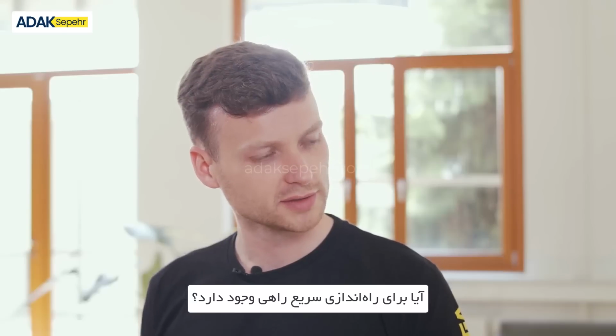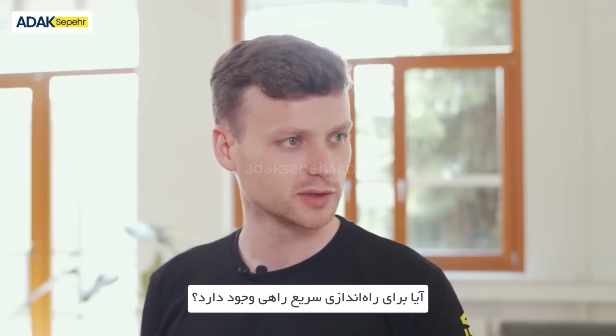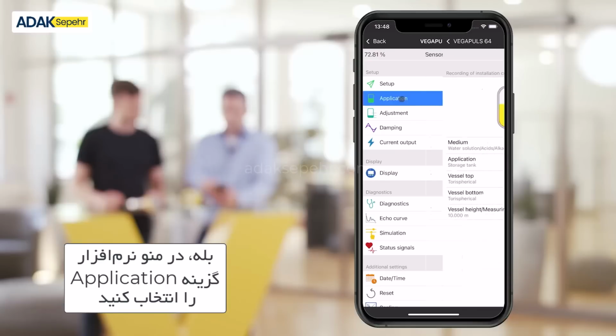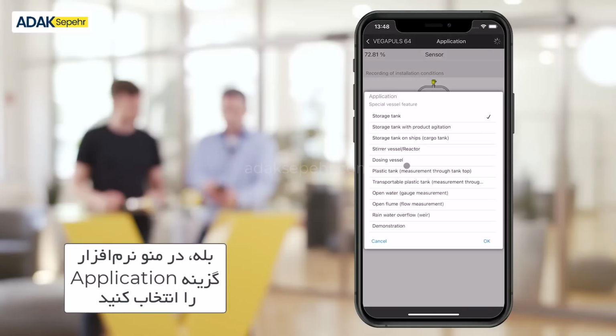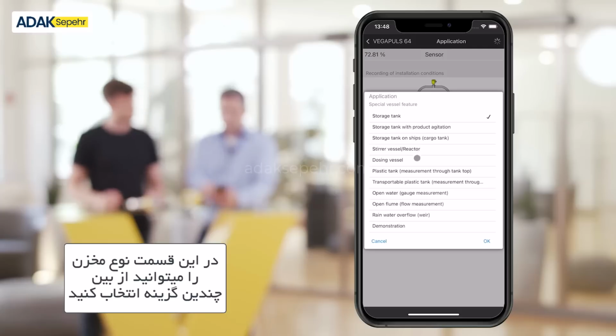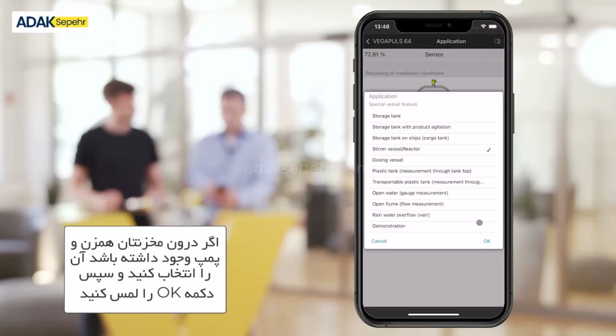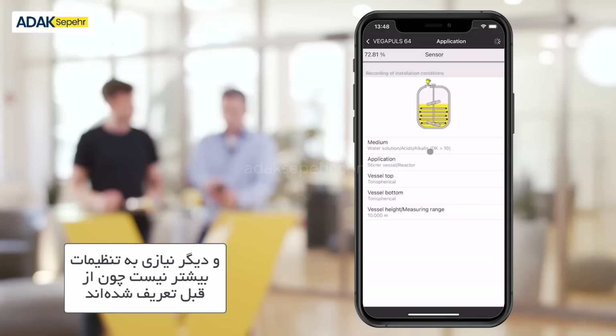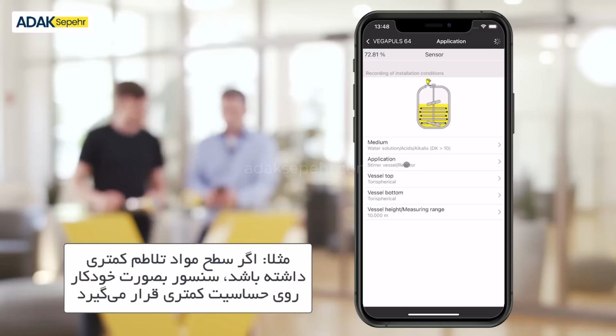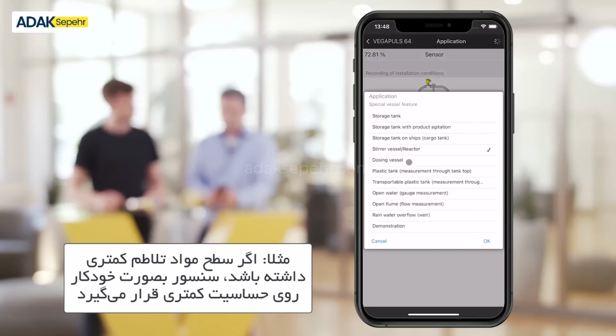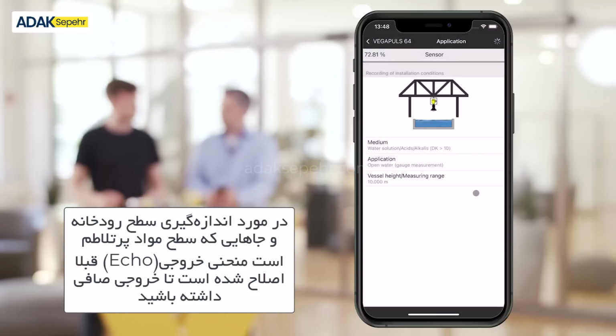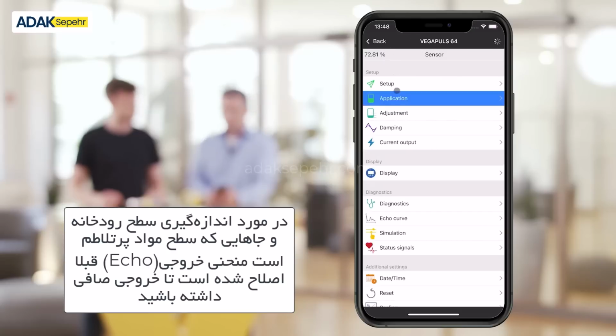Are there any pre-settings that simplify setup and commissioning for the user? Yes. In the application menu, you can choose, for example, between storage tank, stirrer and dosing vessel, and water level gauging. Here, based on our experience, important parameters are already predefined. If, for example, the level changes only slowly, the sensor is set to be less sensitive, as in river level measurement, where there is wave formation, the echo curve is already smoothened, so to speak.